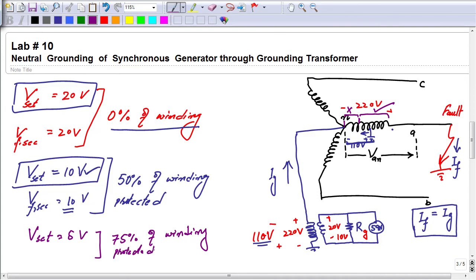In order to protect 100% of the winding, meaning even if a fault occurs on the first turn of this generator winding, that should be protected by the relay. Obviously we will have to set Vset equal to 0 volt. But the problem is we can't set this voltage relay to 0 volt. The reason is that there will be some current or voltage across the primary of this grounding transformer even in normal condition of the generator.